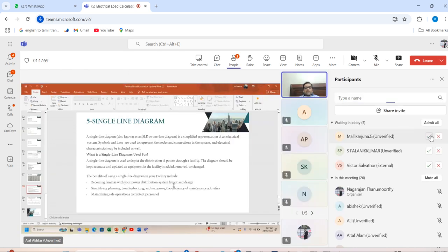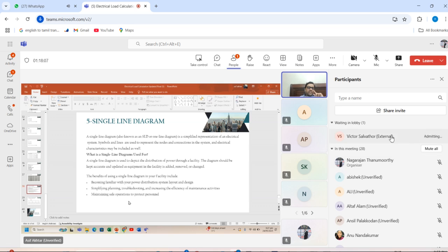What is a single line diagram? A single line diagram, also known as SLD or one line diagram, is a simplified representation of an electrical system. Symbols and lines are used to represent the nodes and connections in the system, and electrical characteristics may be included as well. What is a single line diagram used for? It is used for the distribution of power through a facility. The diagram should be kept accurate and updated as equipment in the facility is added, removed, or changed. This is most important: you have to edit, remove, or change your single line diagram as per your needs. The benefits of using a single line diagram: become familiar with your power distribution system layout and design, simplifying planning, troubleshooting, and increasing the efficiency of maintenance activities. Third, maintaining safe operation to protect personnel.